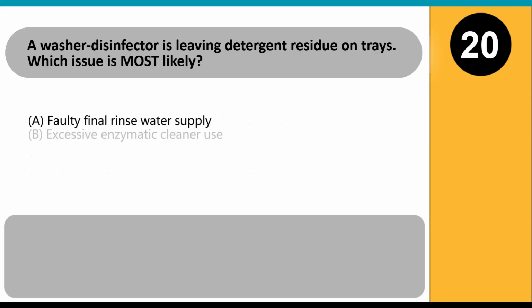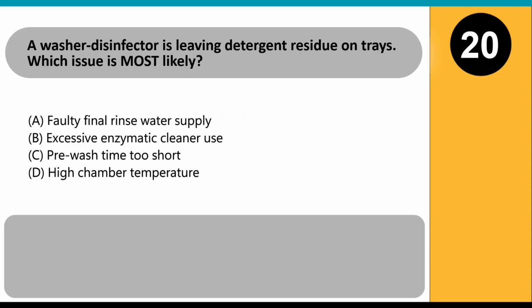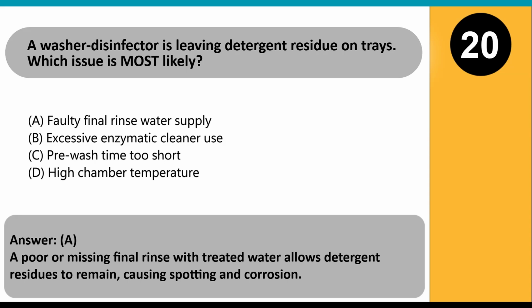A washer disinfector is leaving detergent residue on trays. Which issue is most likely? A. Faulty final rinse water supply. B. Excessive enzymatic cleaner use. C. Pre-wash time too short. D. High chamber temperature. Answer: A. A poor or missing final rinse with treated water allows detergent residues to remain, causing spotting and corrosion.